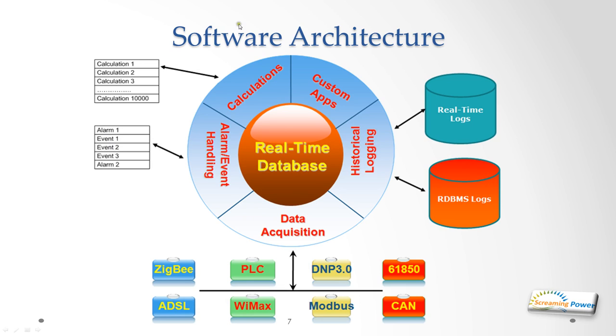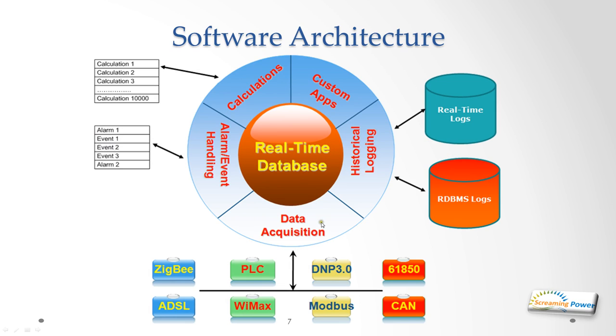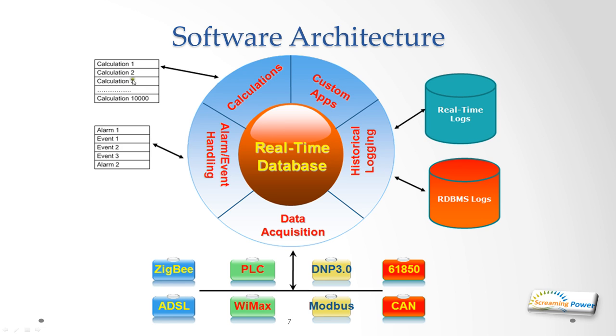The software was specifically designed as a SCADA system. It's not pulled together from different components around the web such as relational databases. It had its own real-time database which we built ourselves and everything went through that database. For example, if you wanted to do calculations you would actually pull data out of the database, do your calculation and put the result back in. In the same way, if you want to do data acquisition we have a standardized data acquisition interface where we write different drivers such as Modbus. Data comes in, is passed into the database, we do what we need to, and if we want to send outputs to the controllers again it goes through the standard data acquisition interface. We did our own real-time logging system which is far faster and far more efficient than using relational database logs.